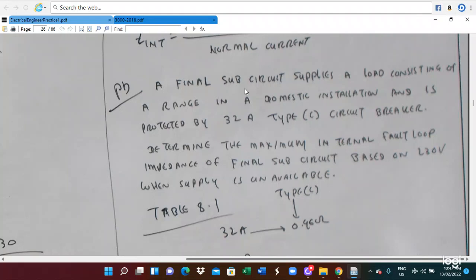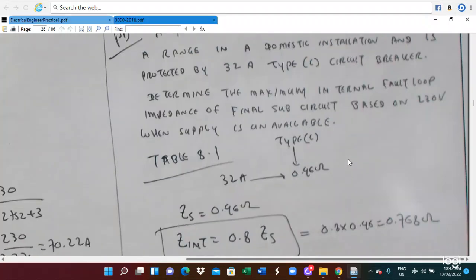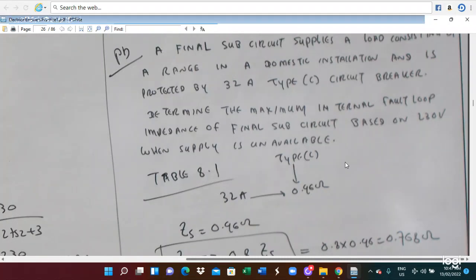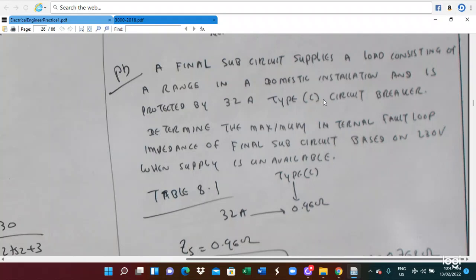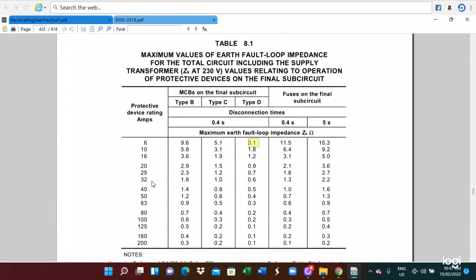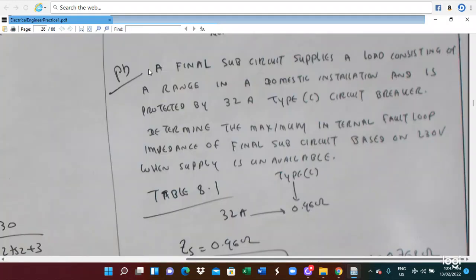Okay, this problem is a final circuit. The final circuit supplies a load consisting of a range in a domestic installation. It is protected by a 32 ampere Type C circuit breaker. The task is to find the maximum internal fault loop impedance and the final circuit, based on a 230 volt supply voltage. Firstly, we have to know about the 32 ampere Type C circuit breaker, so you refer to table 8.1. In table 8.1, for the 32 ampere Type C circuit breaker, the fault loop impedance is 0.96 ohm.